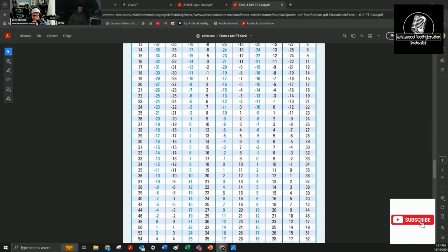One of the things that I found, because I know Kevin does this, but I do as well, is setting the SST, whatever it's supposed to be, on the subcoolers and that. Sometimes that can be difficult because we want it to operate at the temperature that we want, but we don't want it to keep cutting in and out. And so sometimes you have to run a little bit higher than what it says on the actual reefer schedule. Well, I mean, most of the time it's like 10 to 15 pounds higher than what it calls for. Yeah, because otherwise, for some odd reason, probably because the pressure's changing, unless there's an EPR in there, it ends up flooding back hard.